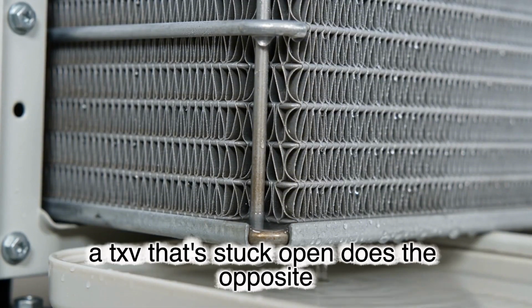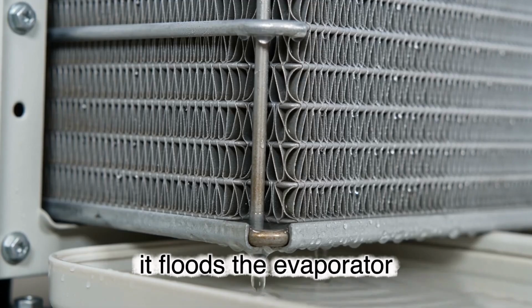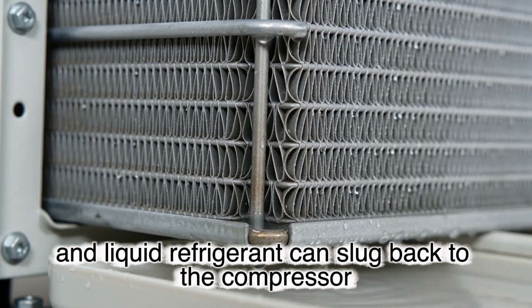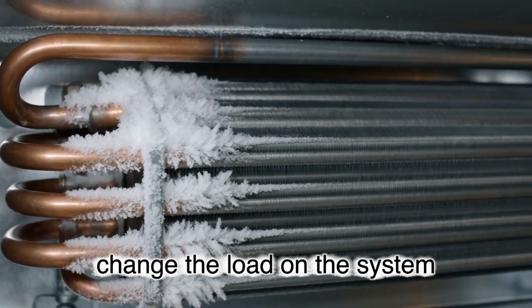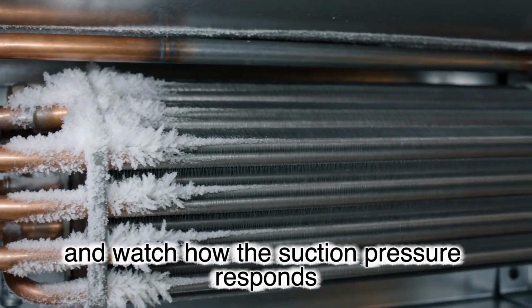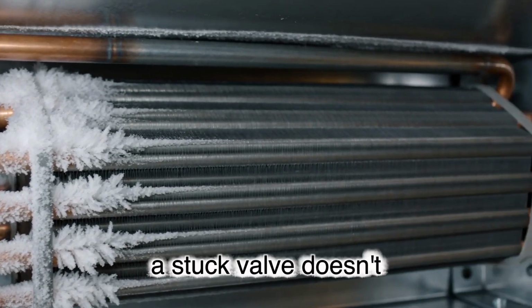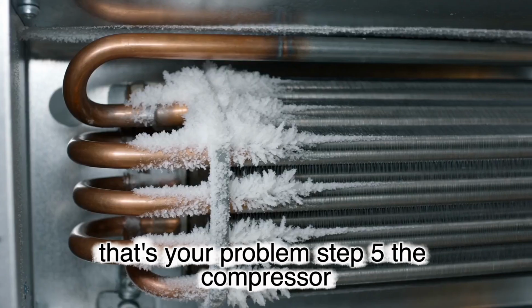A TXV that's stuck open does the opposite. It floods the evaporator, superheat drops to almost nothing, and liquid refrigerant can slug back to the compressor. The diagnostic tell: change the load on the system, and watch how the suction pressure responds. A healthy TXV modulates, a stuck valve doesn't. If the valve isn't responding, that's your problem.